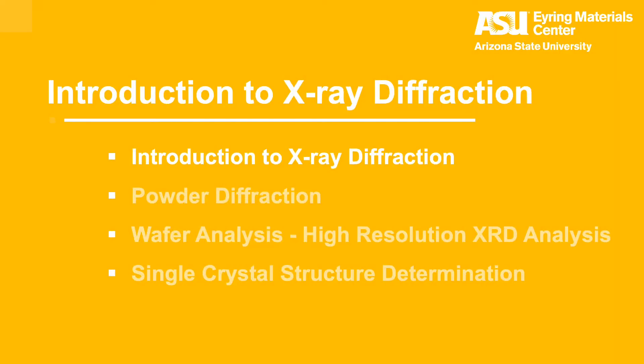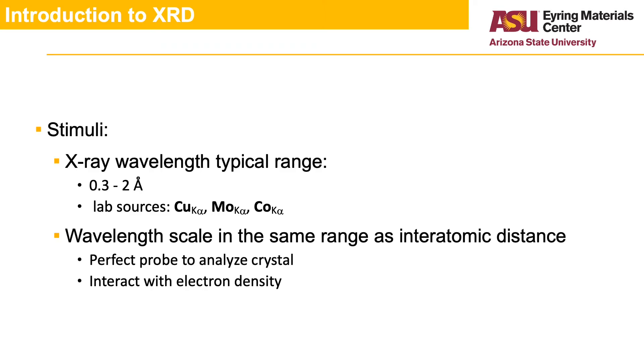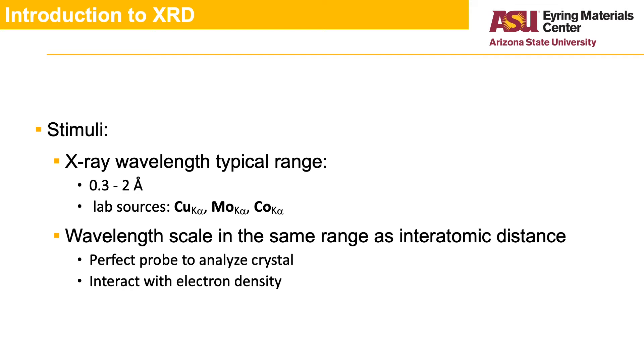In this first section, let's go over some of the basics about X-ray diffraction. In an X-ray diffraction measurement, the sample is probed using X-rays with a typical wavelength in the 0.3 to 2 angstrom range. The typical X-ray lab sources are copper k-alpha with a wavelength of about 1.54 angstrom, molybdenum k-alpha with a wavelength of about 0.71 angstrom, and cobalt k-alpha with a wavelength of 1.79 angstrom. The wavelength of the radiation is in the same range as the interatomic distances in a solid, making it a perfect probe for analyzing crystals.